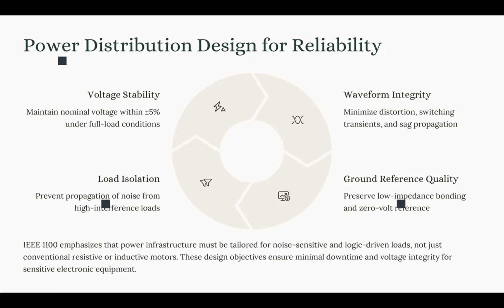So the power distribution system for each zone should be isolated from each other. We shouldn't have one panel board that supplies every piece of equipment in our system. We have to categorize them. We are going to talk about the zones defined in the IEEE 1100, and each zone has to have a different isolated power distribution system.